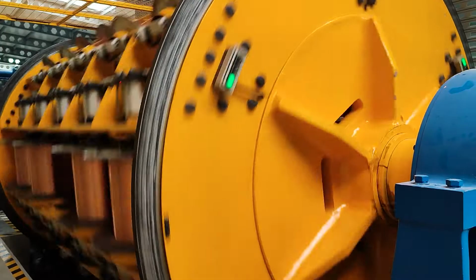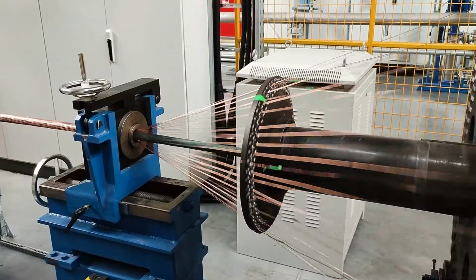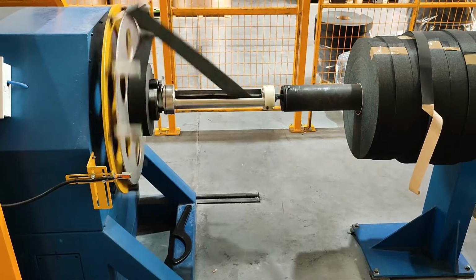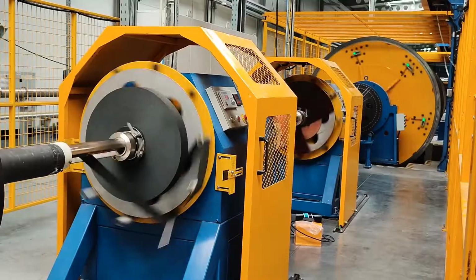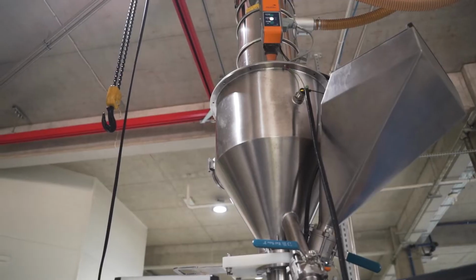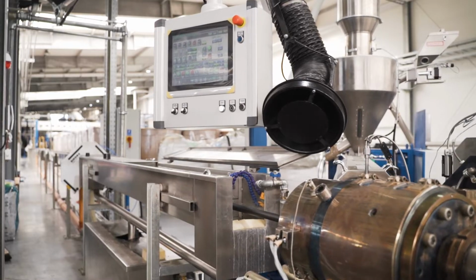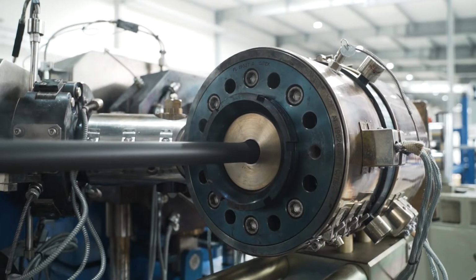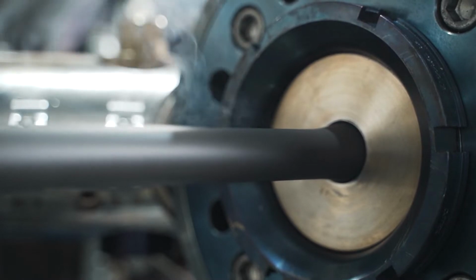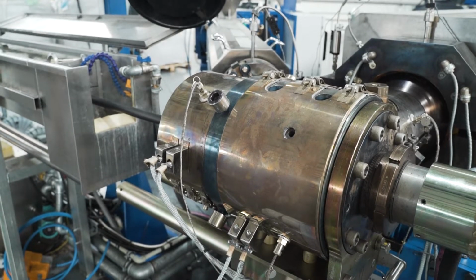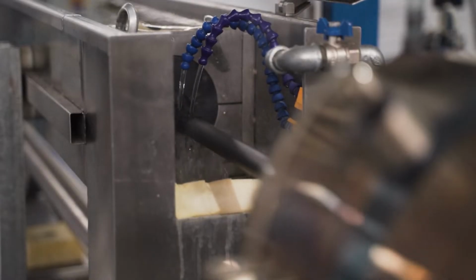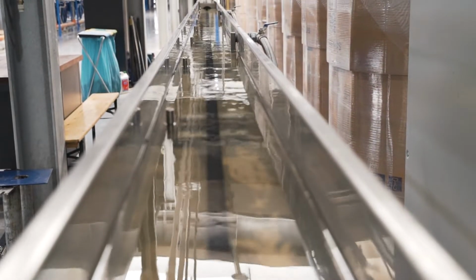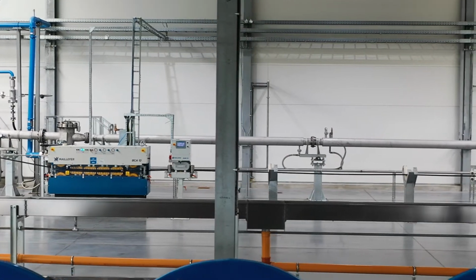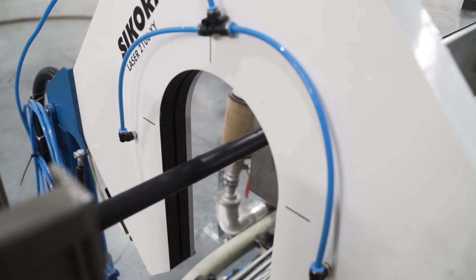In the screening process, a copper metallic screen and sealing tapes are applied. And this is the final stage. Once unrolled and with the aluminium tape applied, a semi-finished product passes through the extruder head. A special plastic mixture is plasticized and pressed under high pressure onto the surface of the cable core. Now it's time to cool down again. The cable goes to the cooling tubs, then receives an identification imprint, and finally goes to the drum reeling device.